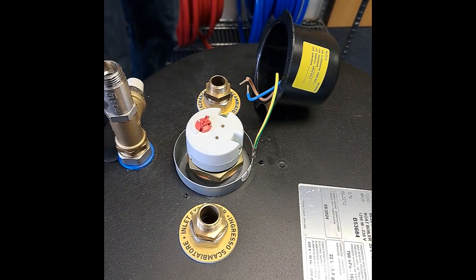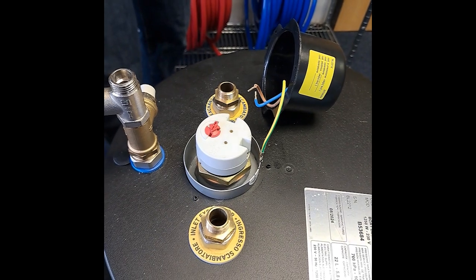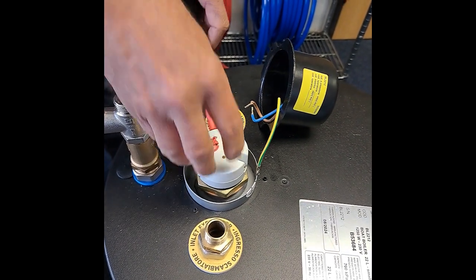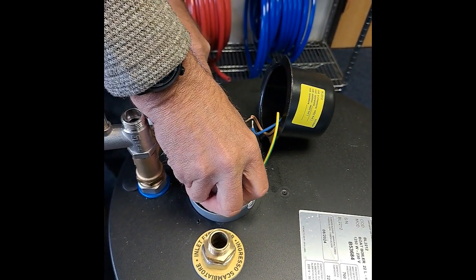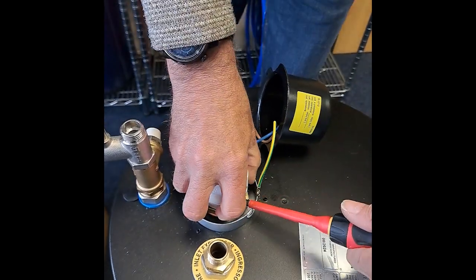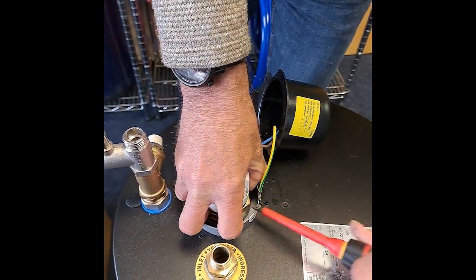Next, we'll remove the thermostat. This has bayonet fittings into the top of the element, and don't be surprised if it's tight. Take a flathead screwdriver and prise it off. Now the thermostat is removed, you can see the bayonet connections that you've just released.